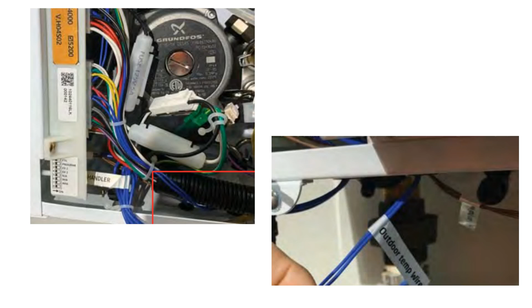First, check the assembly condition of the control board and the temperature sensor wire. Reassemble the control board and the temperature sensor wire. Then check the temperature sensor wire for a short. If it is shorted, then replace the temperature sensor.